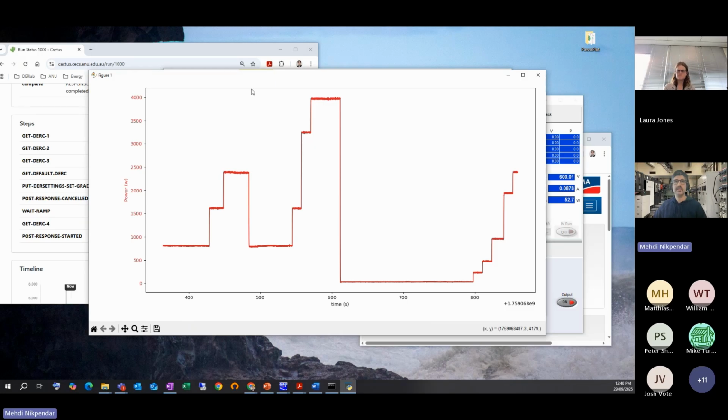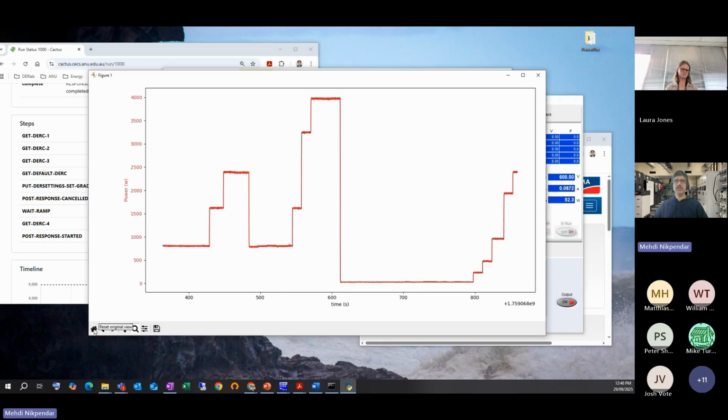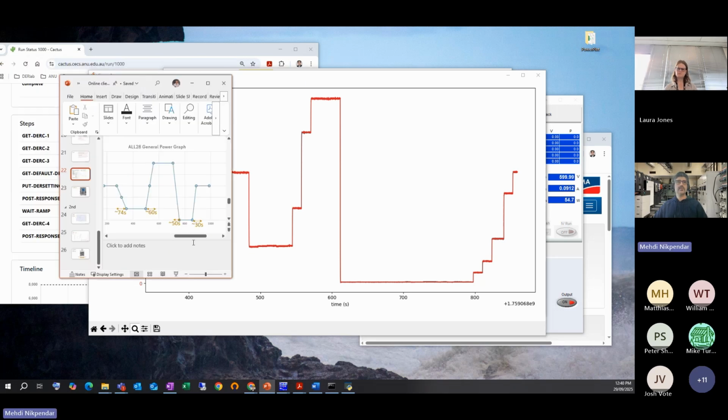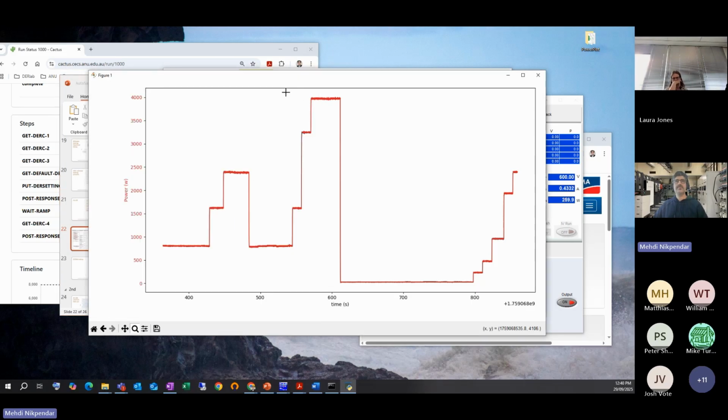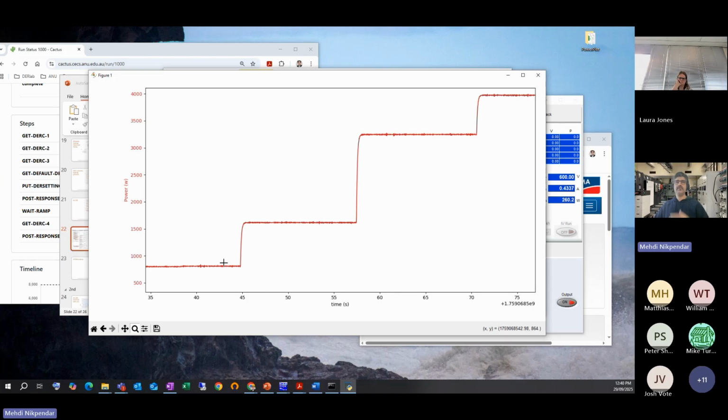So it's interesting that it's following all the commands, but ramp rates are not implemented. So maybe let's look at one of the ramp rates. So from 10% to 50%, let's open this. So we expected from 10% to 50% within 60 seconds. And it's not quite following a ramp behavior. It's just 3 steps. And it doesn't follow that 60 seconds.